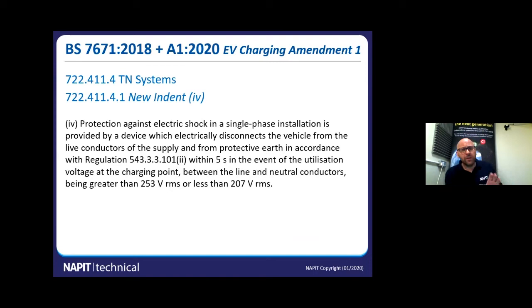Now this device doesn't have to disconnect up to 4 seconds, but it must disconnect within 5 seconds, if it sees the voltage between the line and neutral conductors fall outside of those voltage bands, 207 to 253. So this device needs to be set to operate if the voltage goes outside of those parameters. One of the characteristics of losing a PEN conductor is that the voltage dips and flies all over the place. So if it goes flying up or down, the device will see that. After 4 seconds, it needs to disconnect within the 5 seconds.